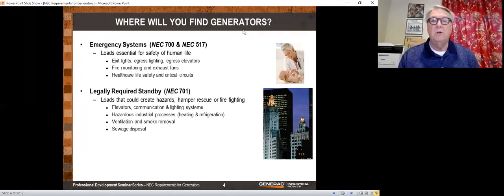So a legally required generator is one that could create hazards, hamper rescue, or firefighting. So elevators, you'll notice that we saw elevators twice, but if they're egress elevators necessary to get out of the building, they're emergency. If there are other elevators that are necessary for firefighting and to help with rescue, but they're not necessary for egress, then they might be legally required. Hazardous industrial processes, ventilation and smoke removal, sewage disposal. So water treatment plants, water supply plants, in many cases are going to be legally required because water is pretty important. And you don't want your sewage plant down in an emergency.